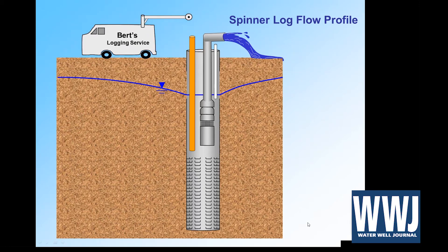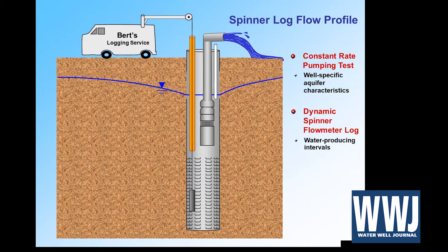The way this works is we turn on the pump and get a little drawdown column. We bring in our logger and he runs what's called a spinner log. A spinner is an impeller just like a flow meter in a pipeline. This is run down at a constant rate of speed while we're running the pump, so water is coming in and flowing up to the pump intake. As this tool flows past, we can measure the different gallons per minute coming in at different depths. In one day's time you can gather a whole lot of information from a well.